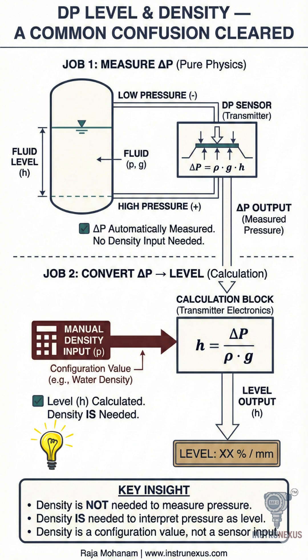No density input means correct pressure, wrong level. The fluid creates the pressure automatically, but the transmitter needs density to understand what that pressure means in terms of level.